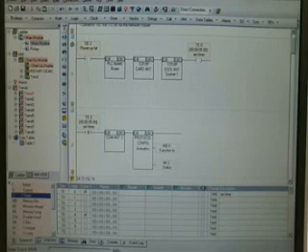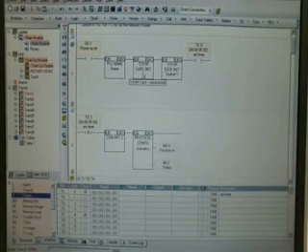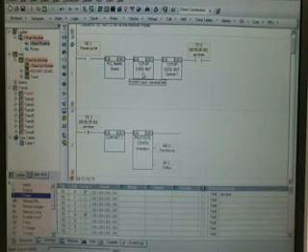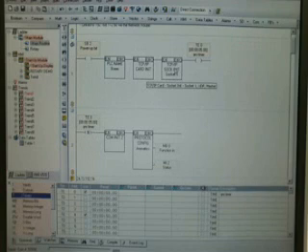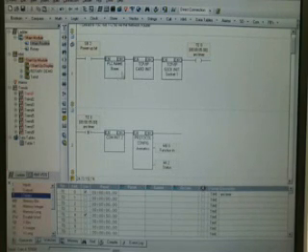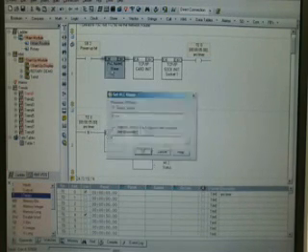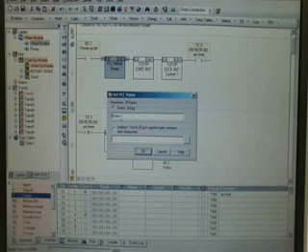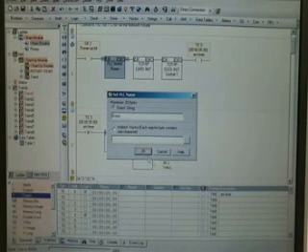Notice in network one, on power up, we're going to set a PLC name. We also have a TCP IP card initialization, and we will also initialize a socket over TCP IP. So the PLC name function block, simply type in the name you want to call your PLC, and in this case it's called BRAS.